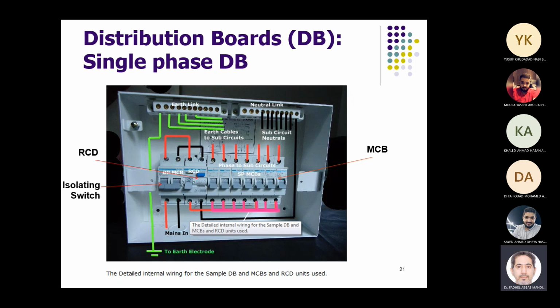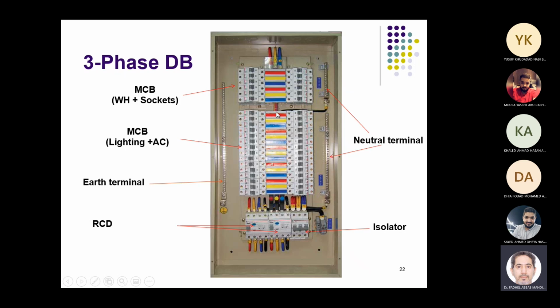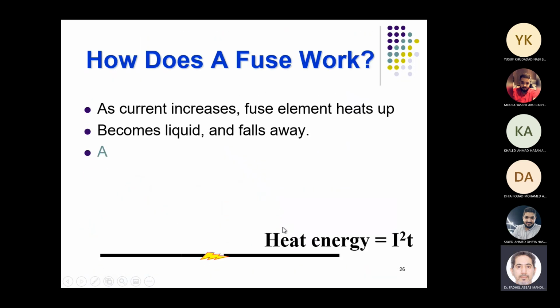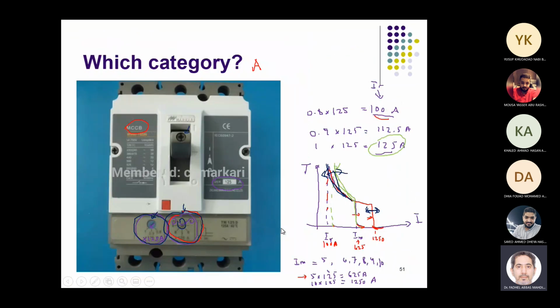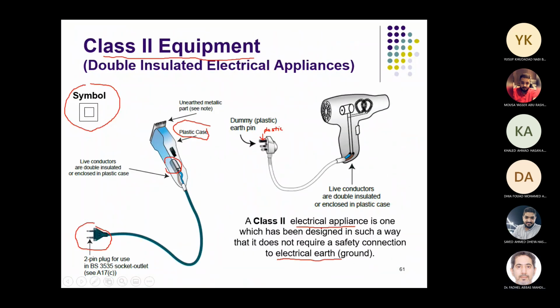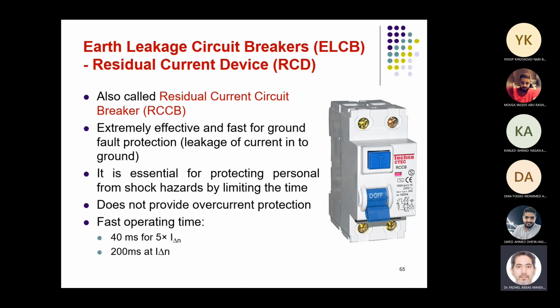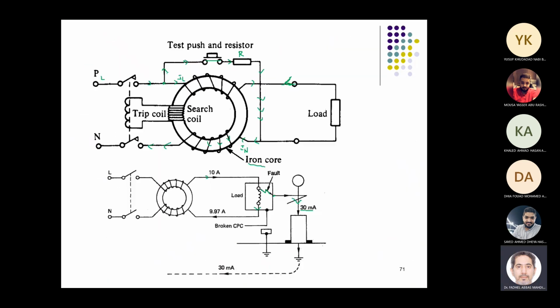So if you learn from these high voltage equipment, you will be able to understand this low voltage equipment easily. And this is a distribution board, a three-phase distribution board, and these are the small breakers, and these two are the RCDs, or residual current devices. Residual current devices can detect a very small current that goes to earth, and therefore provide electrical shock protection. Their principle is very simple. The currents passing in the line and neutral are the same, so the magnetic fields generated by the current in the line and neutral cancel each other.